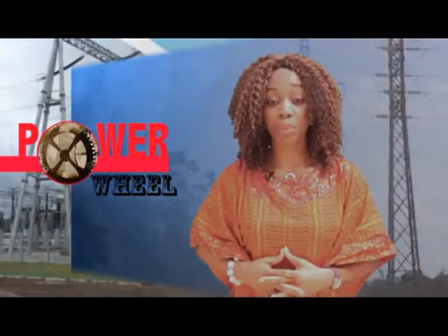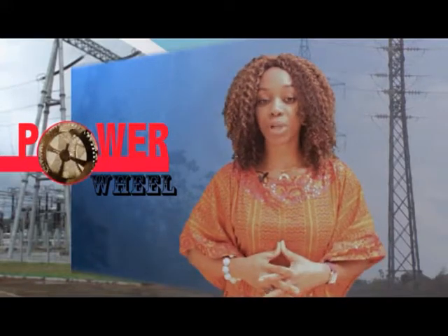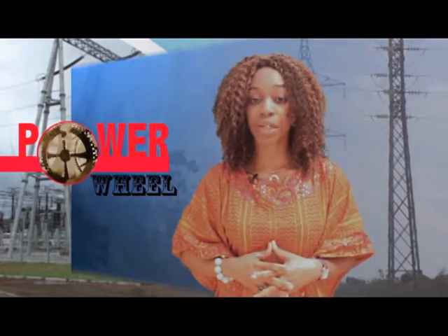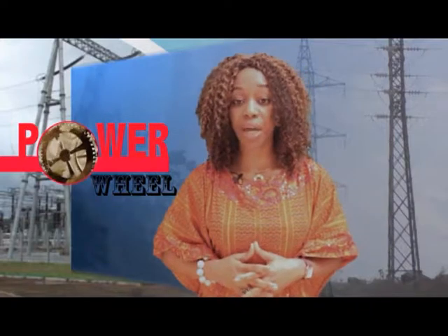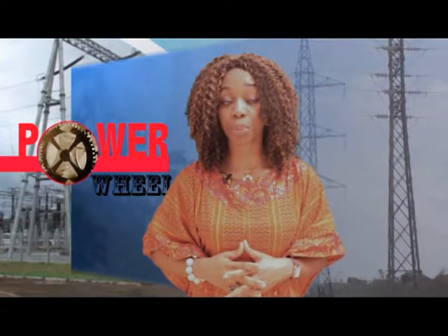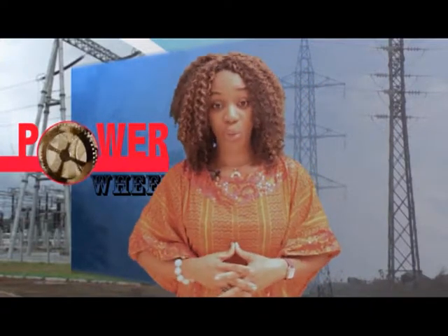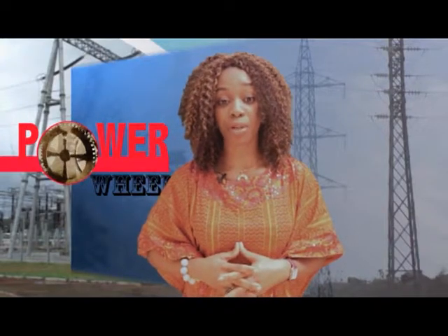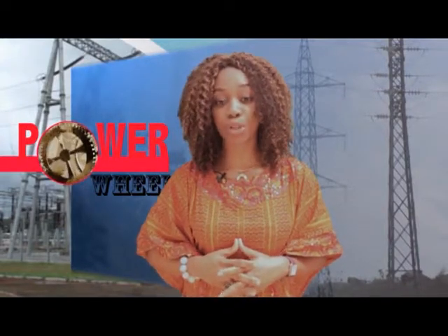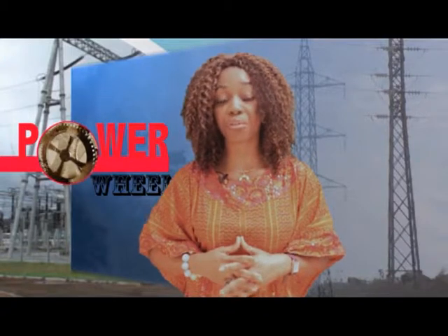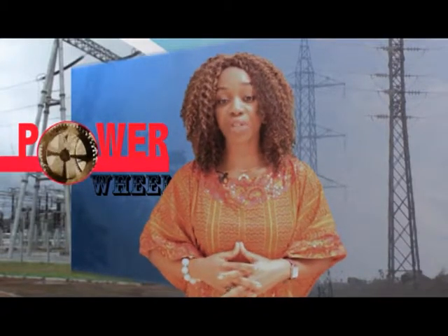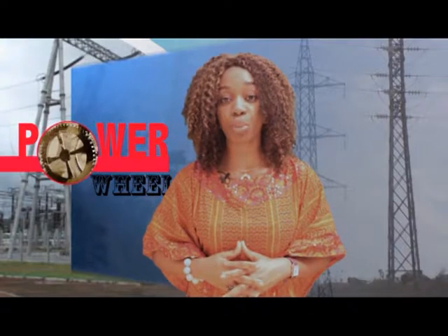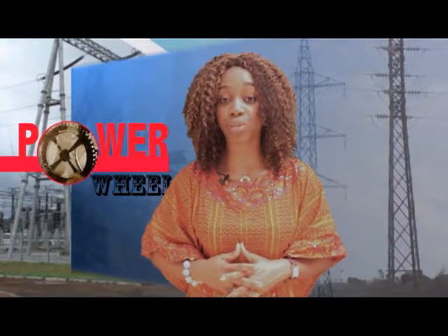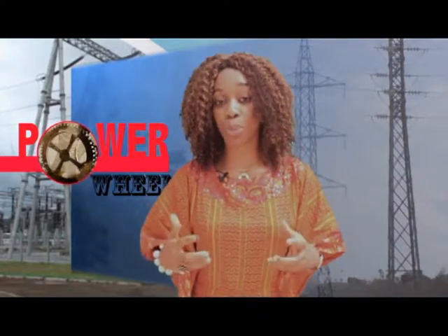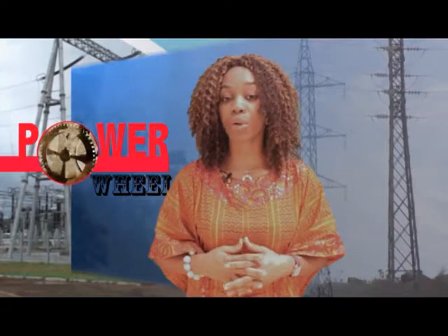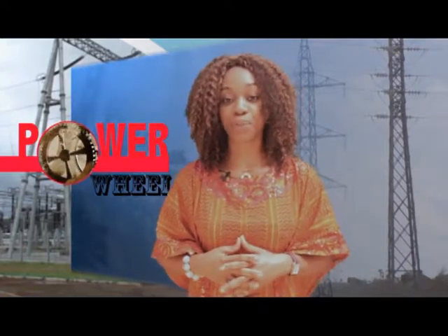Last week on the program, we told you about efforts by the Transmission Company of Nigeria, TCN, to replace the faulty 60 MVA power transformer in Karu substation. Today, we are glad to inform you that TCN has almost completed the installation of a brand new 60 MVA transformer at the 132 by 33 kV Karu transmission substation to boost power supply to residents of Karu and its environs in Abuja.